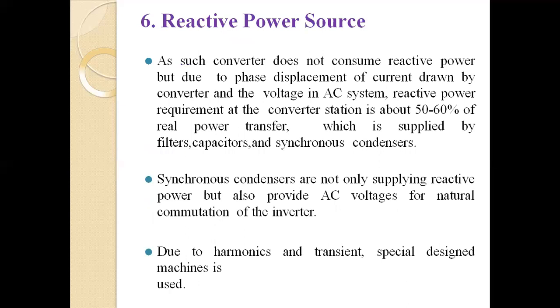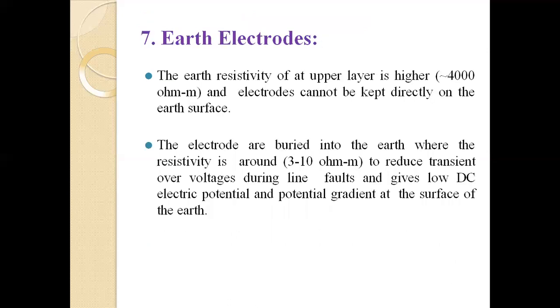Next part is the reactive power source. The converter itself does not consume reactive power, but due to the phase displacement between the current drawn by the converter and the voltage in the AC system, the reactive power requirement at the converter station is about 50 to 60% of the real power transfer, which is supplied by the filter, capacitor, and the synchronous condenser. Synchronous condensers not only supply reactive power, but also provide AC voltage for the natural commutation of the inverter. Due to the harmonics and transients, a specially designed machine is used.